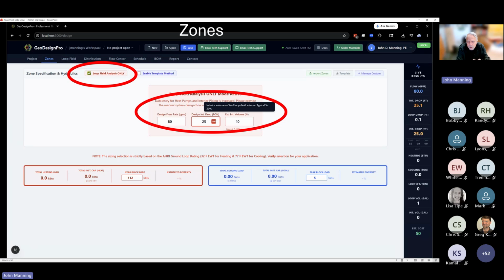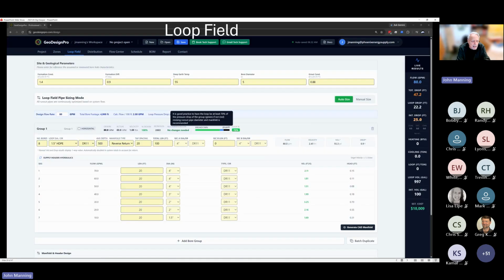And the other thing that I want to point out, as you tab through the various input fields, you'll get these tooltips that automatically pop up and give you a little guidance as to what the software is looking for. So from there, you go right to the loop field tab. And in this particular case, I've got one group of 8 bores. Each bore is using 1.5 inch polyethylene DR11, 500 foot deep, with a reverse return manifold. The tap spacing is roughly 20 feet spacing between the bores. The runout pipe is 100 feet to get to the middle of the reverse return manifold. Then the program automatically suggests 4-inch pipe.